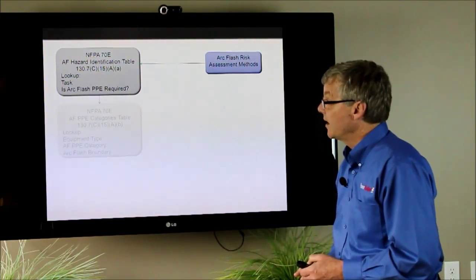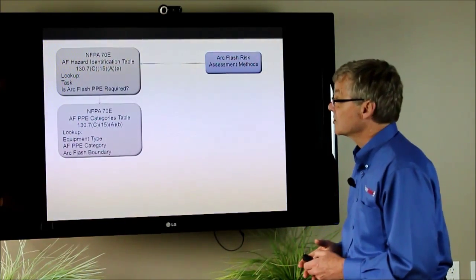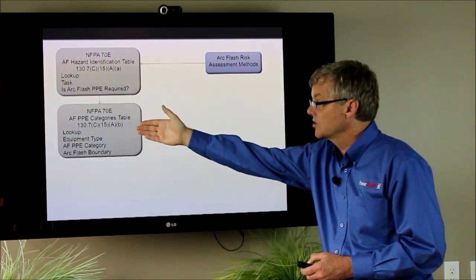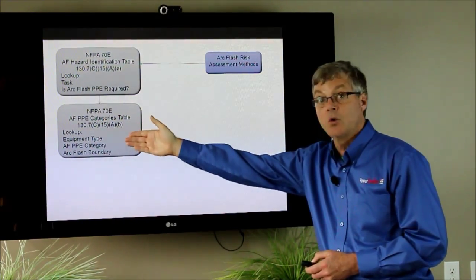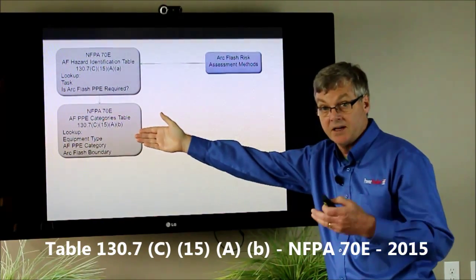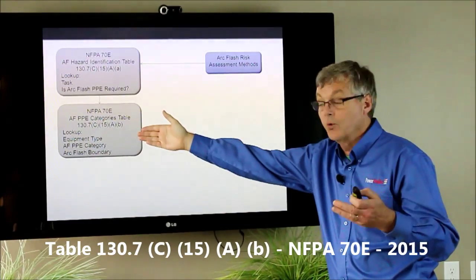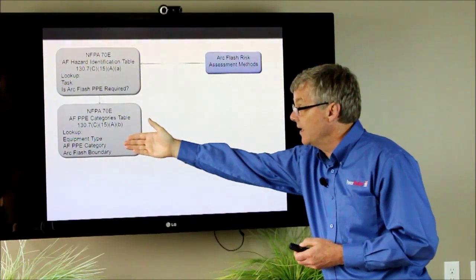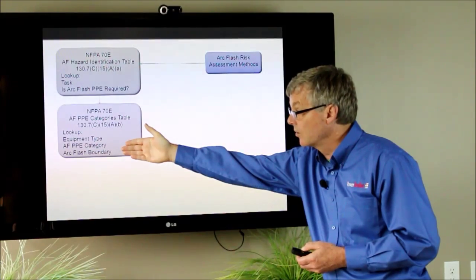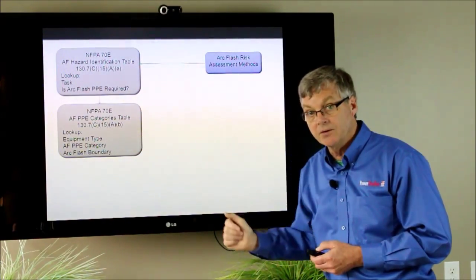Once you find out that yes there is arc flash PPE required, then you go to what's called the arc flash PPE categories table and you look up the equipment type that you're working on. So the type and piece of equipment you're working on based on also voltage as well. And then you look and it'll tell you what the arc flash PPE category is and what the arc flash boundary is.